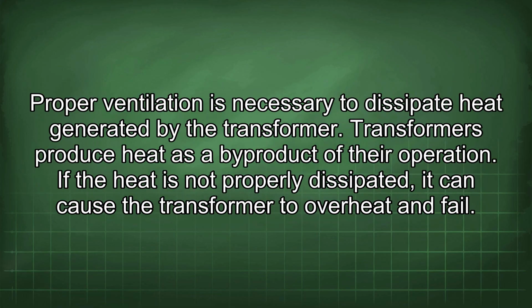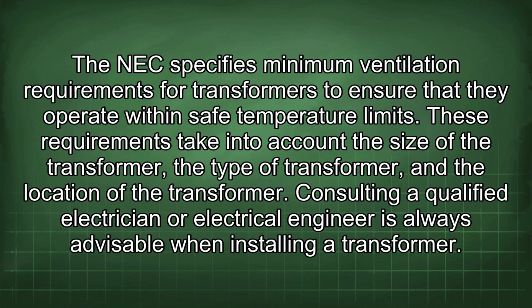Proper ventilation is necessary to dissipate heat generated by the transformer. Transformers produce heat as a byproduct of their operation. If the heat is not properly dissipated, it can cause the transformer to overheat and fail. The NEC specifies minimum ventilation requirements for transformers to ensure that they operate within safe temperature limits. These requirements take into account the size of the transformer, the type of transformer, and the location of the transformer.